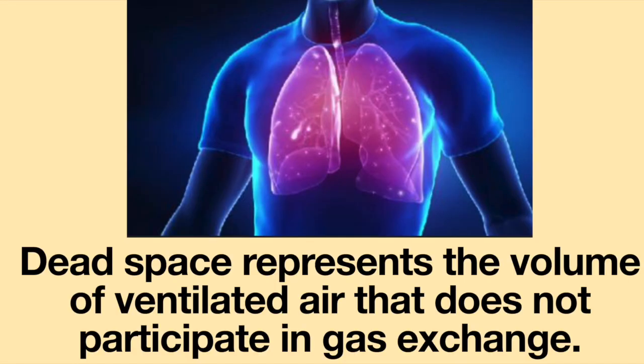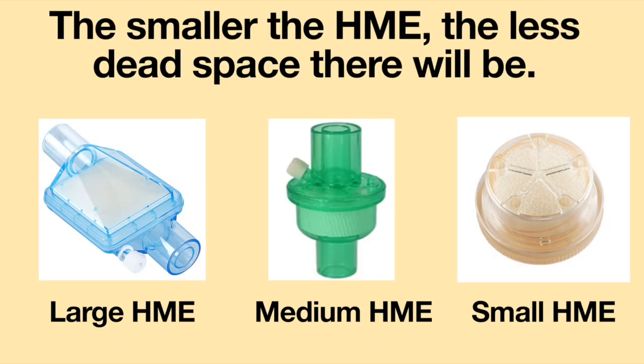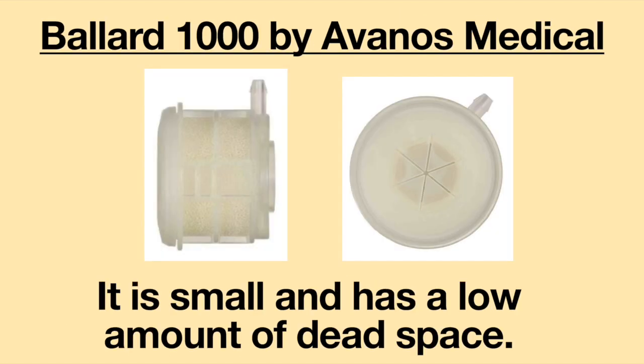In certain individuals, dead space can be an issue. Simply, dead space represents the volume of ventilated air that does not participate in gas exchange. For HMEs, this means the smaller the HME, the less dead space there will be. There is an HME called the Ballard 1000 by Avanos Medical, which is small and has a low amount of dead space.